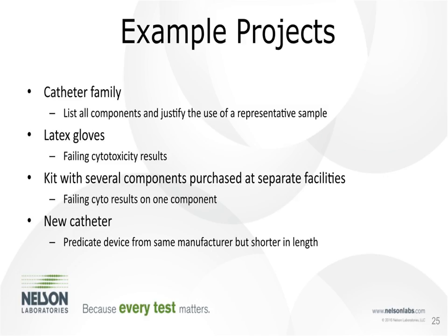For this one, I just wanted to point to something that was mentioned in the US FDA guidance document, where they talk about use of predicate devices. It's great when you're using one of your own devices as a predicate device because you have all the proprietary information on the processes and the materials, which is not usually shared if you take a competitor's predicate device, because you really don't know all of the details typically. So these were some great examples of projects for BERs and how we put that all together, and why an evaluation report is really beneficial, because none of this was straightforward.